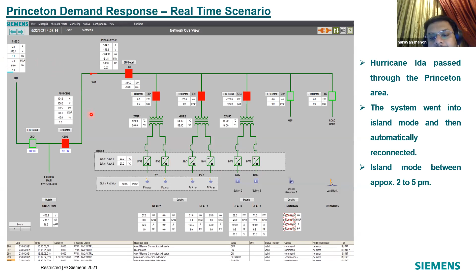This was in fact appreciated by Princeton University too, because there was a seamless transfer. Though the entire area of Princeton had a 4-hour power cut during the hurricane period, there was seamless transfer and no power cut within this entire facility. The battery basically gave the reference voltage and frequency to continue running the PV system, even though there was no grid power.